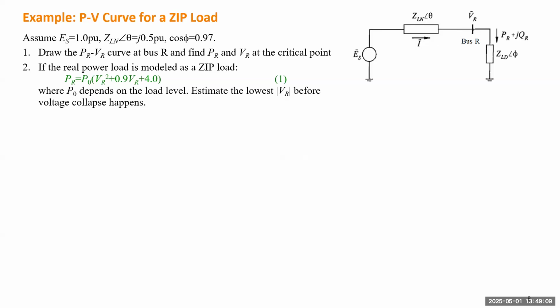Okay, so let's take a look at one example. We try to solve when the voltage collapse can happen for a specific system with a specific load model. This is still that radial system. We give it some values. We assume the voltage source has 1 per unit voltage, the line impedance is 0.5 per unit, so it has no resistance, and the power factor is 0.97. We want to draw the PV curves for that load bus, considering a ZIP load. This P0 depends on the load level, so we can change P0 until the PV curve and this load curve become tangent at a certain point. That will be the voltage collapse point. We want to find that point.